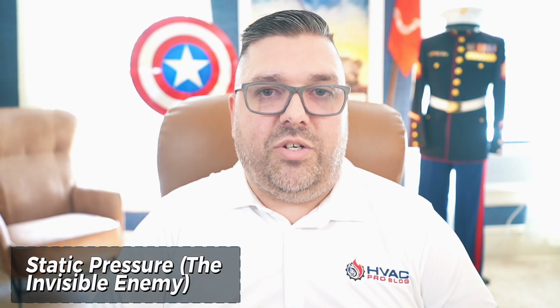Let's talk about static pressure, what I call the invisible enemy. Think of static pressure like blood pressure for your HVAC system. Too high and something's gonna fail. Here's how to spot it before it becomes a problem, and more importantly, how to explain it to customers in a way that positions you as the expert. Static pressure problems don't announce themselves with loud noises and obvious failures. They just slowly strangle your system's performance while driving up energy costs and reducing equipment life. Most contractors never measure it, which means they're flying blind.